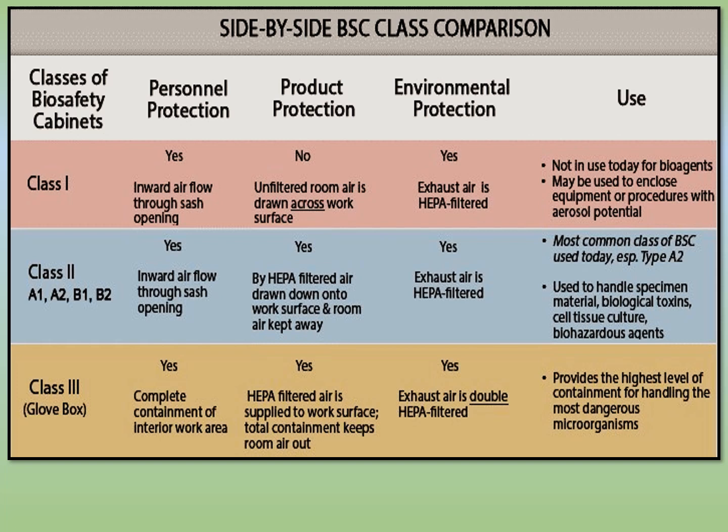The users and the applications have already been discussed. Class 1 biosafety cabinet allows users to deal with low to moderate risk bioagents, usually non-pathogenic organisms. In class 2 biosafety cabinets, the users deal with pathogenic or infectious agents, whereas in class 3 the users work on the most dangerous microorganisms that may cause life-threatening diseases, and diseases that sometimes come without any pre-treatment or vaccination.